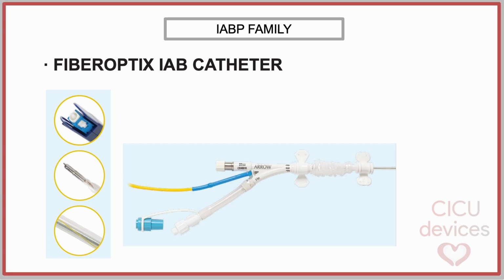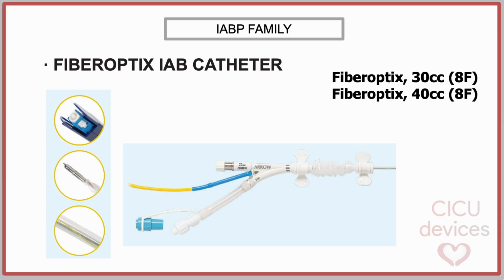The fiber-optics IABP catheter incorporates an integrated fiber-optic pressure sensor located at the catheter tip, enabling direct measurement of central aortic pressure. The real-time aortic pressure signal enables the Teleflex intra-beat algorithm, which automatically optimizes balloon inflation and deflation on a beat-to-beat basis. The fiber optics catheter has an external diameter of 8 French and is available in 3 balloon volumes: 30 milliliters for patients shorter than 162 centimeters, 40 milliliters for patients between 162 and 182 centimeters, and 50 milliliters for patients taller than 182 centimeters.